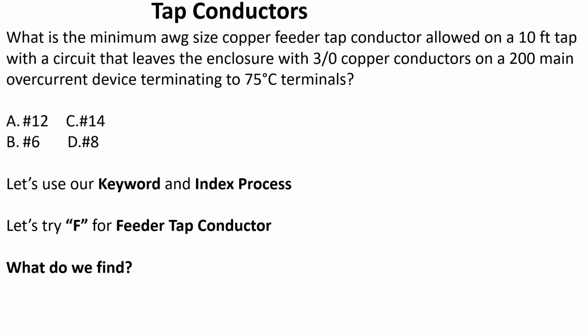Let's go ahead and pause the video now. I want you to head to F in the index, and I want you to look for feeder tap conductor. Okay, so when we get to F in the index, we do find feeders. We do not find feeder tap conductor specifically, but now we're in feeders. We feel like we're in the right section. We're on page 838 in the third column. Up at the top, we see feeders. Now let's look down in alphabetical order and see if we can find anything about taps. So we skim through till we get to the T, and we do find taps. So we found feeder and taps. So we feel like we're in the right section.